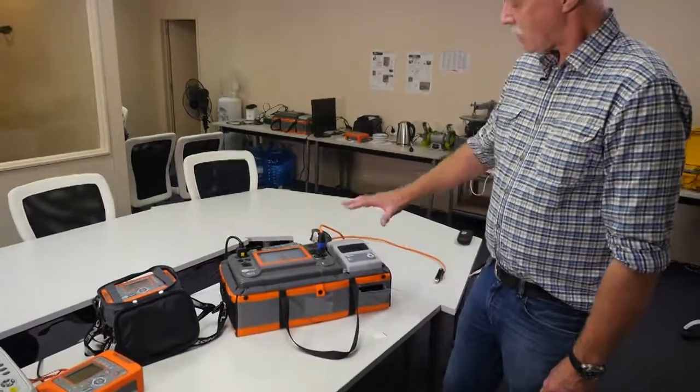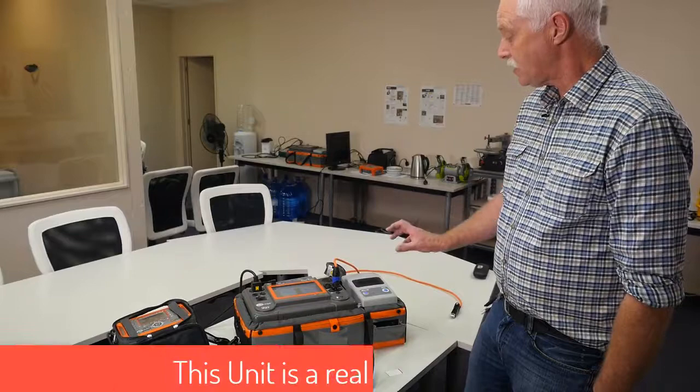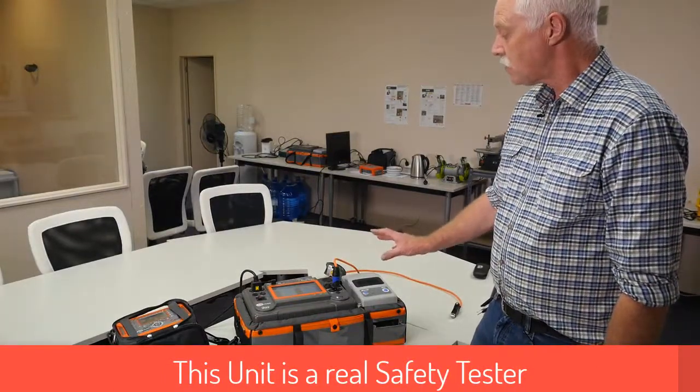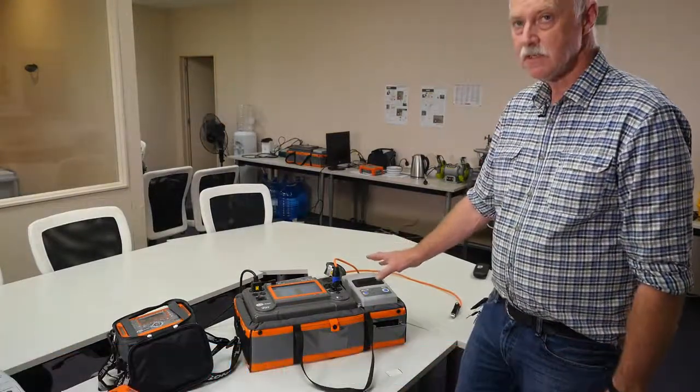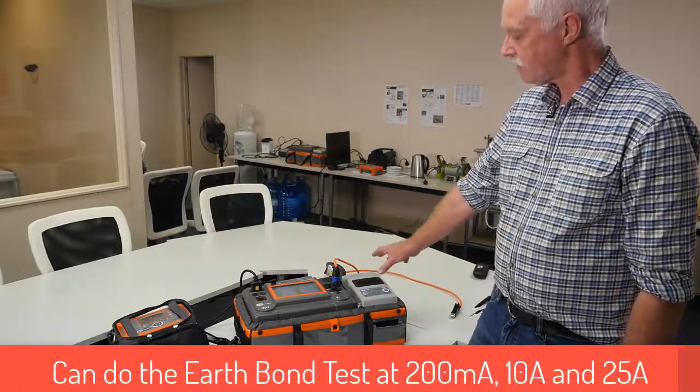So it's got a lot of features. But not only does it have all those features, it's a real tester. It actually is a safety tester. It can test at 200 milliamps, 10 amps and 25 amps.